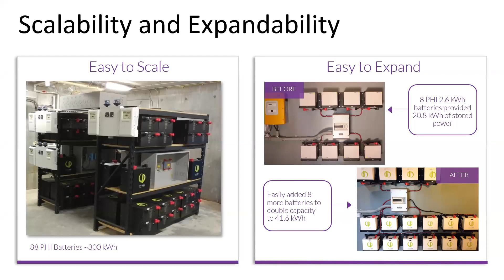Probably more relevant to this presentation is expansion. We allow new batteries to be placed on old battery systems, so you can actually expand the system. This can be super helpful if you're an installer — maybe you put in a system and the customer doesn't properly convey their critical loads for the backup system. You can go back and add batteries, so you're not stuck with whatever you sized in the beginning. You can fix it and add more storage, and that might just be because the customer's needs grow.